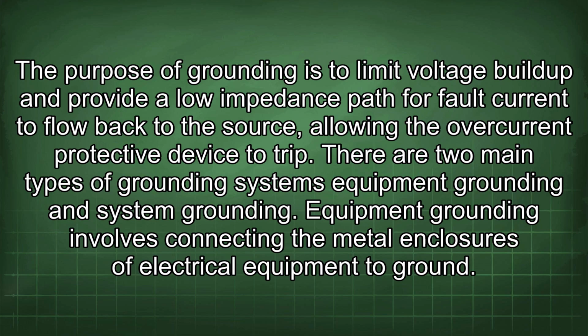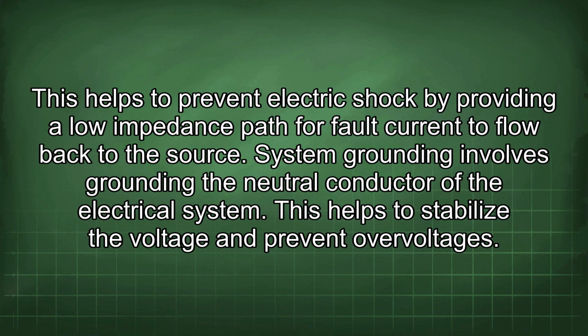Equipment grounding involves connecting the metal enclosures of electrical equipment to ground. This helps to prevent electric shock by providing a low impedance path for fault current to flow back to the source. System grounding involves grounding the neutral conductor of the electrical system. This helps to stabilize the voltage and prevent overvoltages.